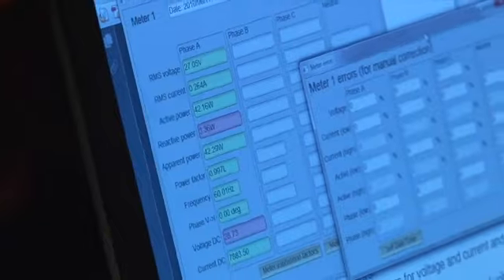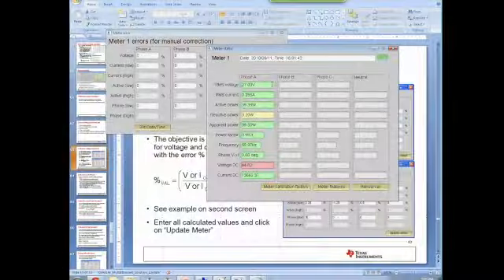So it's best to calibrate these whenever the readings are green, so we know it's taking nice, stable readings. It also takes time to re-inject. If we enter a calibration factor, it has to add that back into the DSP algorithm that McRae talked about earlier, so that can take a while to stabilize. We just wait till they're green and go from there.